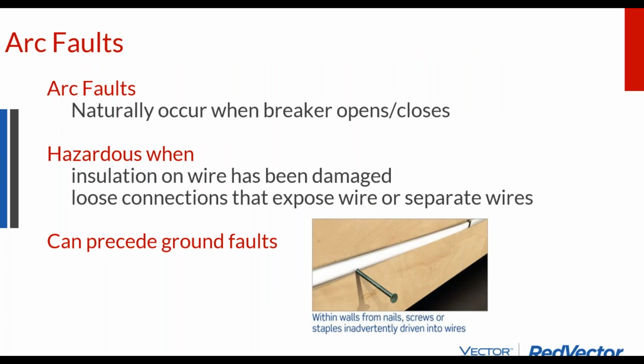So arc faults can be difficult to detect. They can continue without much interruption to the service if it's a minor arc fault. So you might get some kind of phantom errors that you can't diagnose particularly well without any breakers tripping. That can be an arc fault, and they can precede ground faults.